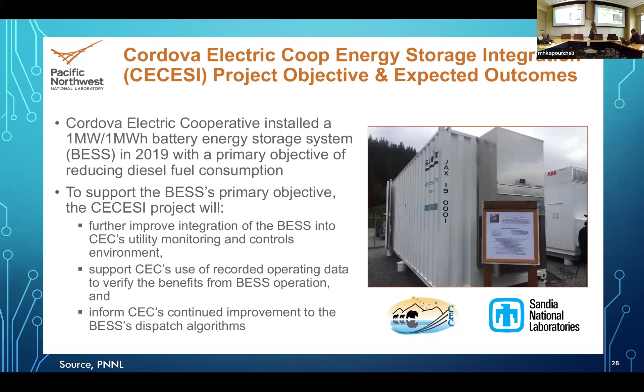The same SAFT battery team that did the Golden Valley Electric nickel cadmium system years ago. There's a picture of the battery, and it's amazing: two containers, one is the lithium-ion batteries, the other is a 1 MVA ABB inverter set that can switch from grid-following to grid-forming. It's an isochronous mode, setting the frequency when it's in operation for that whole system, so anything else connected follows the heartbeat set by this battery. What's good is you can set it up for basically continuous charge and discharge, so if you want it in that role, it could be on all the time, in this case releasing the hydro to maximize energy output.